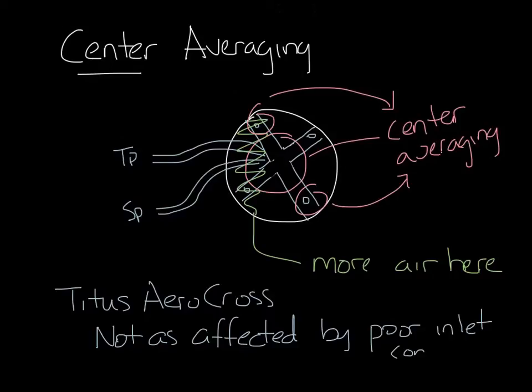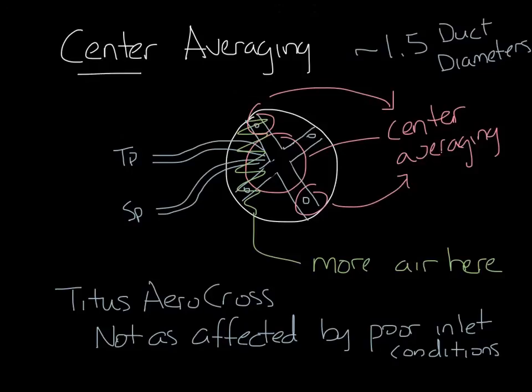Because of this, you need less straight duct into the box inlet, about 1.5 duct diameters for our flow sensor, compared to about 3 duct diameters for a linear averaging type sensor. So that's the difference between center averaging and linear averaging flow sensors.